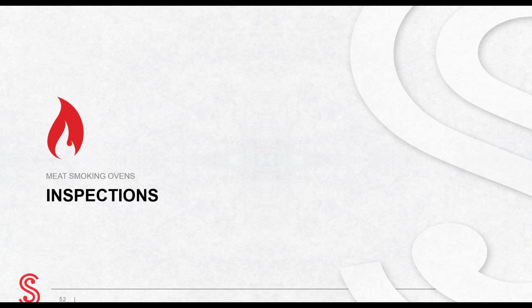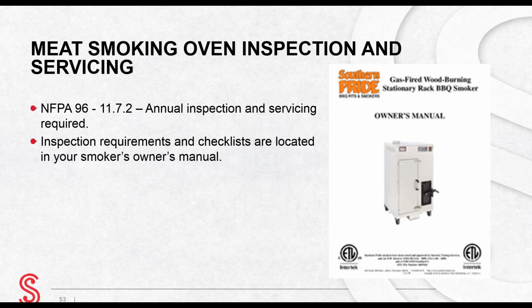Lastly, let's talk about inspections required for the entire meat smoking unit. Inspection and servicing of the cooking equipment must be made at least annually by a properly trained and qualified contractor according to NFPA 96 11.7.2. Inspection requirements and checklists are located in your smoker's owner's manual. This is a picture of a Southern Pride owner's manual.